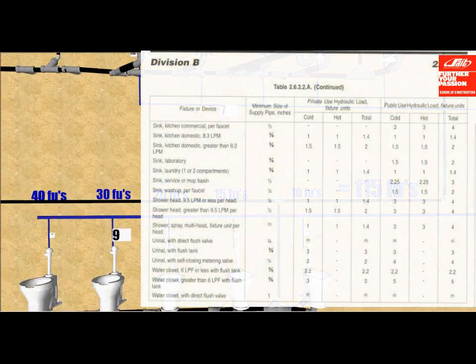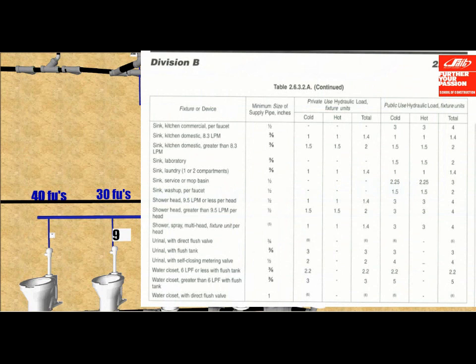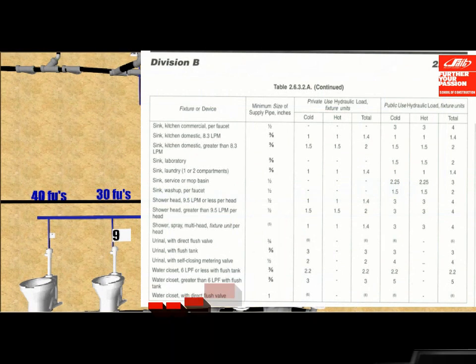Finally, in order to calculate number nine, which is the drop piece to the flushometer toilet, you would look at table 2632A under the very bottom figure, which is the water closet with direct flush valve.